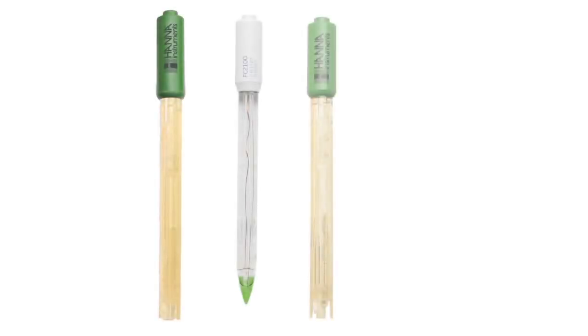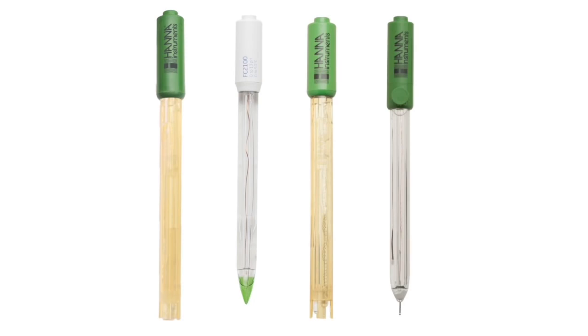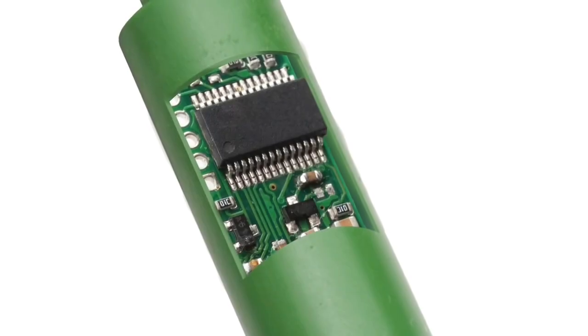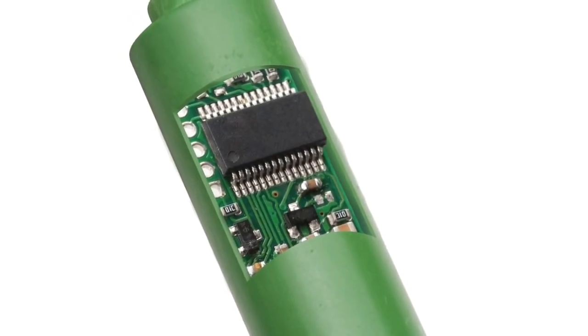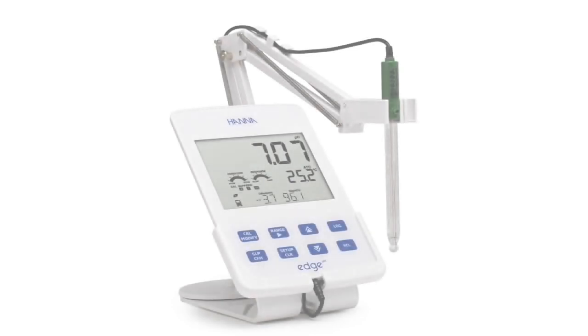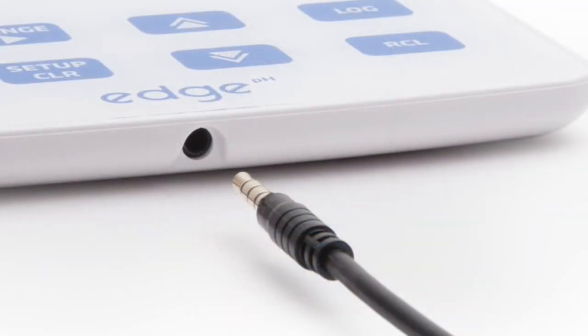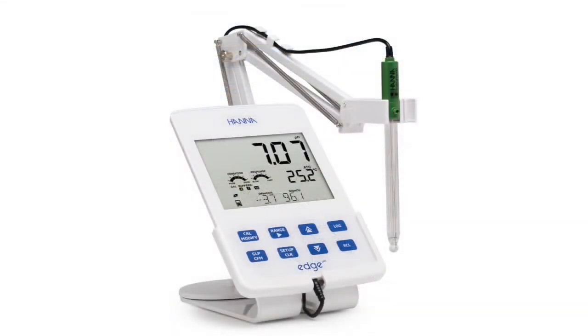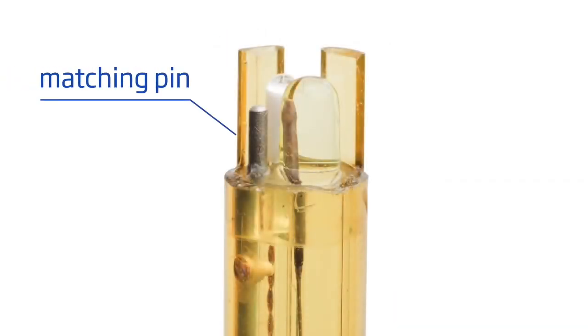Hanna Instruments offers a wide range of optional pH and ORP digital electrodes, including ones designed for specific applications. Since the electrodes are digital, calibration information is stored in the electrode rather than the meter. The use of digital electrodes on the HI2002 also allows the meter to automatically identify electrodes once they are plugged into the meter. This feature permits electrodes to be swapped without having to calibrate each time a new electrode is connected. An optional matching pin is available on some electrodes.